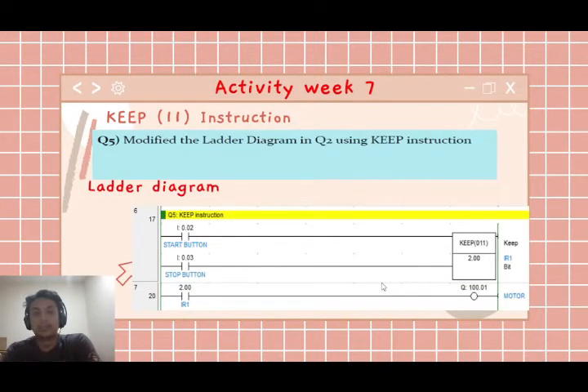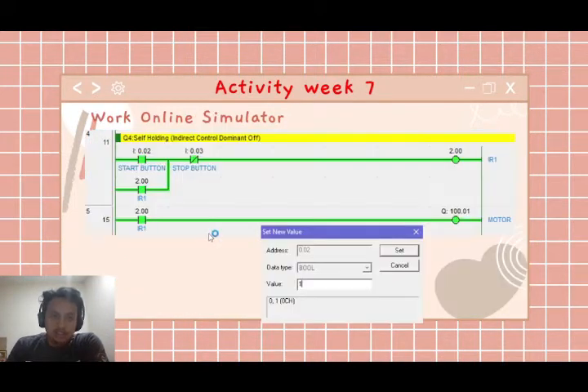The last one is about the keep instruction. Modify the ladder diagram in Q2 using the keep instruction. This is the ladder diagram for keep. We must have the start button and stop button together with keep, and the memory is connected with the motor. When we give the value to the start button, the motor will run, and we give the stop button to the motor.